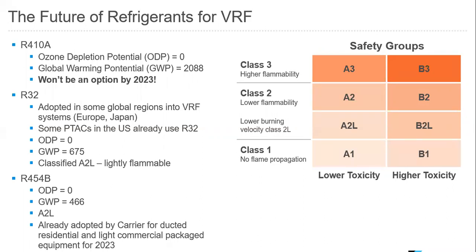So R32 is classified as an A2L, which says it's lightly flammable. So when you look at it on the chart, it is a class 2 refrigerant. Other manufacturers are also considering a class 2 refrigerant with a safety rating that fits in the safety group of A2L, and that refrigerant is called R454A, R454B, and that refrigerant has already been adopted by Carrier for ducted residential and light commercial package equipment for 2023.